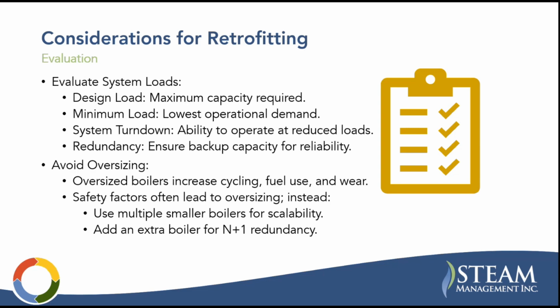So as far as your evaluation, you want to evaluate your system loads. What is your design load? What is your minimum load? What is the system turn down requirement, as compared to the boiler turn down requirements? What is your redundancy requirement? Are you in a hospital? If you're in a school, you've got to have some redundancy for reliability of the system. And you want to avoid oversizing.